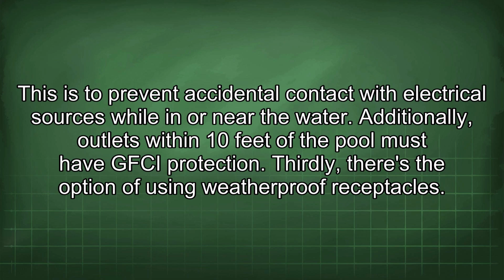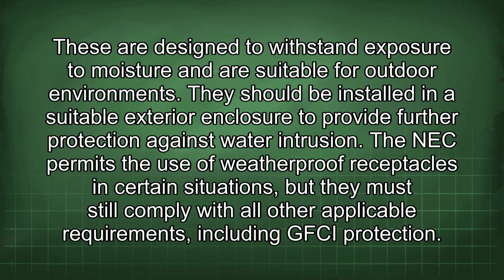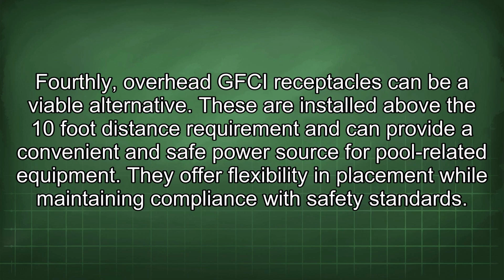Thirdly, there's the option of using weatherproof receptacles. These are designed to withstand exposure to moisture and are suitable for outdoor environments. They should be installed in a suitable exterior enclosure to provide further protection against water intrusion. The NEC permits the use of weatherproof receptacles in certain situations, but they must still comply with all other applicable requirements, including GFCI protection. Fourthly, overhead GFCI receptacles can be a viable alternative.